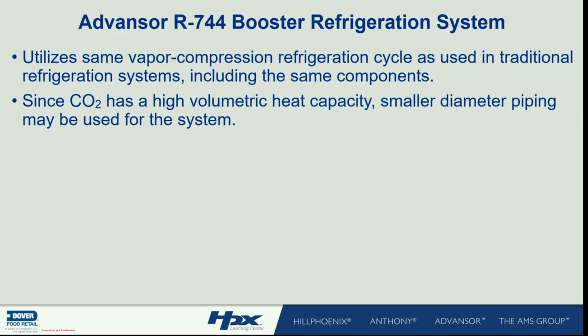Everybody's saying it, and if you want to prove it, don't believe anybody here. Go to the liquid line. Go into the store, look at the liquid line. Go to a 12-foot open case, look at the liquid line, the suction line, and the risers. Go to a 404 store, 448, whatever you can legally put in California, and do the same thing. Make note of the line sizes, that's all I'm asking. You'll see what we mean when we talk about high volumetric capacities.